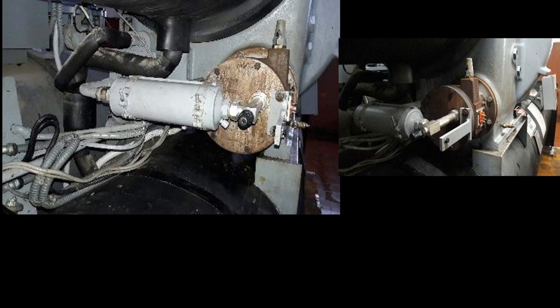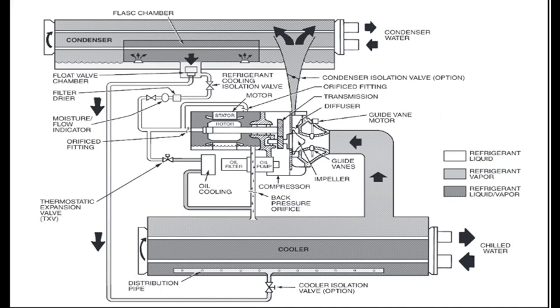From the reservoir, oil is distributed to key components. In one stream, oil is sprayed as a fine mist over the drive transmission gears to ensure an even coat. In another stream, oil is forced at high pressure onto the bearings and thrust bearings to cover all surfaces. Oil from the drive transmission stream is collected in a reservoir and sent back to the vessel so the sump pump can continue circulating oil. Oil from the bearings stream is sent directly back to the heat exchanger, as it will be much hotter and needs cooling. A third stream is sometimes used to control the position of vane guides, using oil pressure to hydraulically move their position.